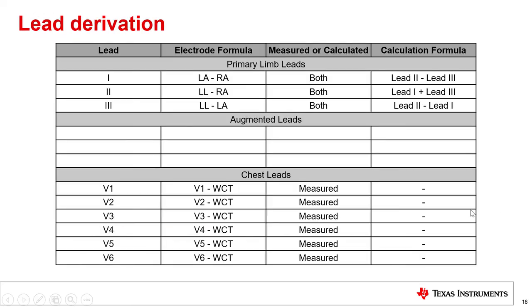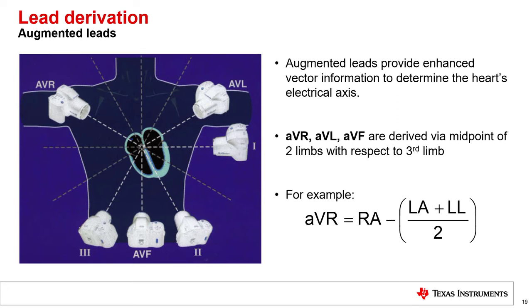Next, we will cover the final group, the augmented leads. These leads provide enhanced vector information, which is used to determine the heart's electrical axis within the body, and provide physicians with even more information to make a diagnosis. The augmented leads are named augmented vector right, augmented vector left, and augmented vector foot, or AVR, AVL, and AVF, respectively. Each augmented lead uses one of the primary electrodes as the positive input, while the average of the remaining two is used for the negative input. For example, AVR is measured as the RA electrode minus the average between LA and LL.